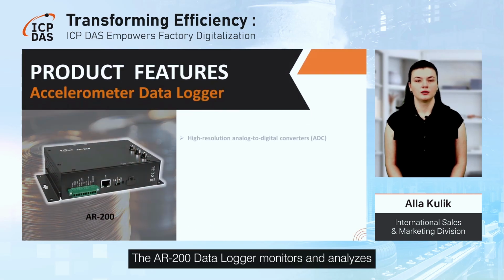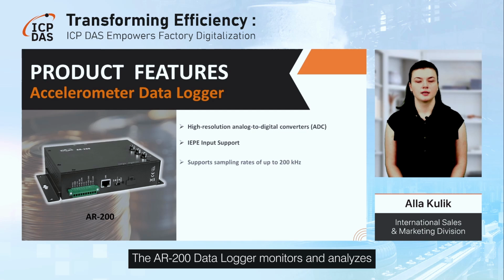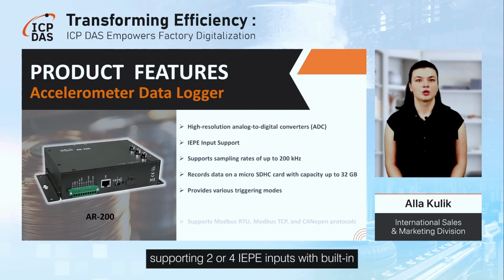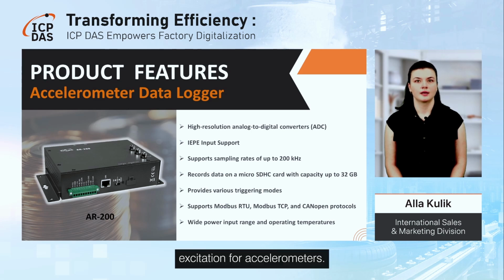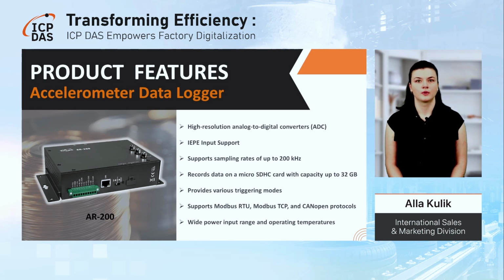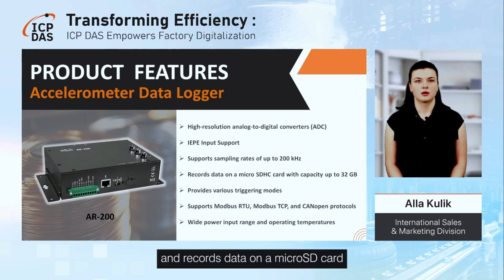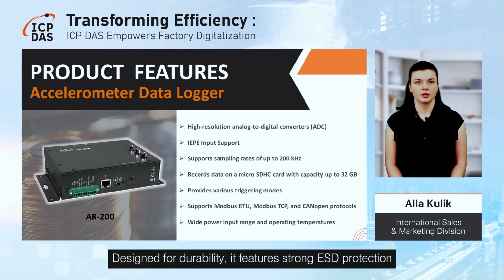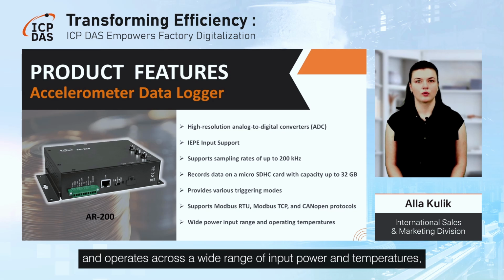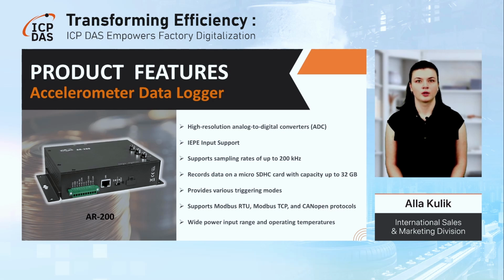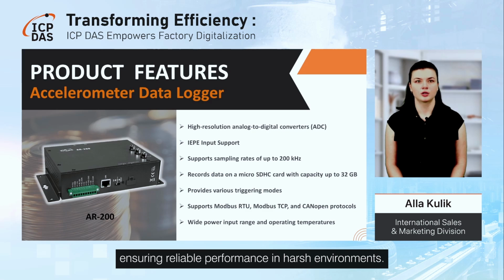The AR-200 data logger monitors and analyzes machinery vibrations, supporting 2 or 4 IEPE inputs with built-in excitation for accelerometers. It offers adjustable sampling rates and records data on a micro SD card with multiple trigger options, including push button and scheduled modes. Designed for durability, it features strong ESD protection and operates across a wide range of input power and temperatures, ensuring reliable performance in harsh environments.